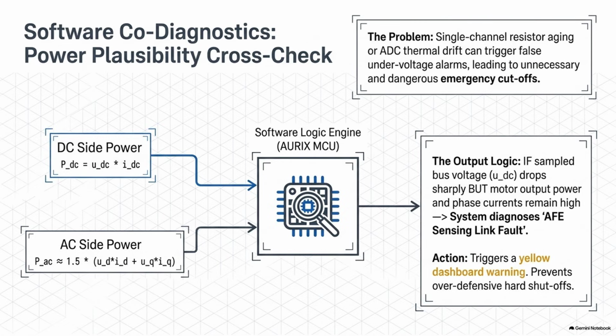Without electrocuting the microchip, yes. So the first step is using a network of precision resistors. These act as a voltage divider, shrinking that massive 800-volt signal down to a tiny microscopic analog signal, usually swinging between -1 volt and +1 volt. It creates a completely proportional miniaturized reflection of the main power line. If the 800-volt line drops by 10%, this tiny 1-volt signal drops by exactly 10%.